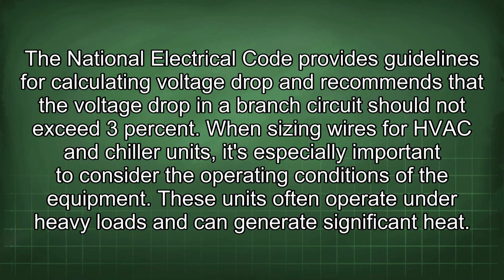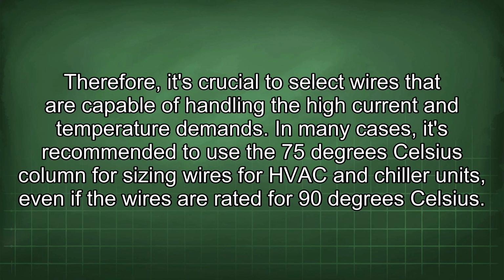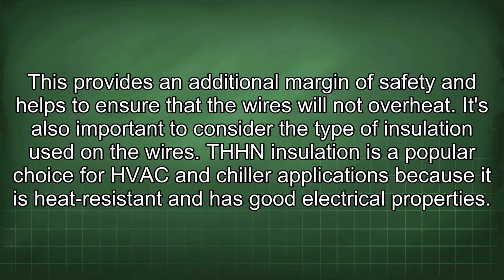When sizing wires for HVAC and chiller units, it's especially important to consider the operating conditions of the equipment. These units often operate under heavy loads and can generate significant heat. Therefore, it's crucial to select wires that are capable of handling the high current and temperature demands. In many cases, it's recommended to use the 75 degrees Celsius column for sizing wires for HVAC and chiller units, even if the wires are rated for 90 degrees Celsius. This provides an additional margin of safety and helps to ensure that the wires will not overheat.